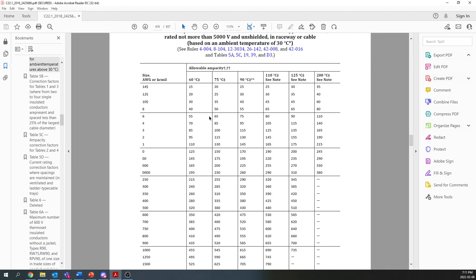So we have to go up a size. We know to go to 65, and taking off 10% of 65 is much more than 50. So we're good with, so now that higher ambient temperature has forced us to derate our wires.